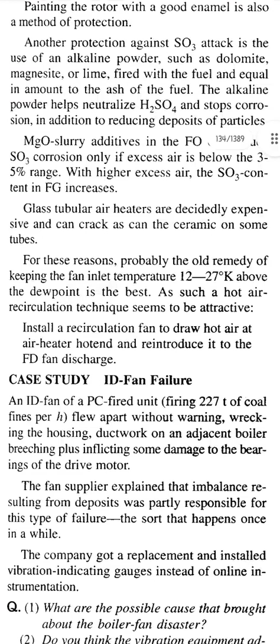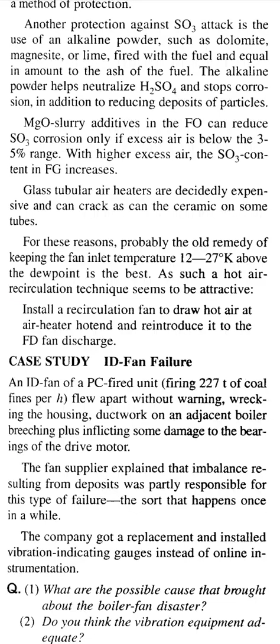MgO slurry additives in the FO can reduce SO3 corrosion only if the excess air is below the 3 to 5% range. With higher excess air, the SO3 content in FG increases. Glass tubular air heaters are decidedly expensive and can crack, as can the ceramic on some tubes. For these reasons, probably the old remedy of keeping the fan inlet temperature 12 to 27 degrees Kelvin above the dew point is the best.